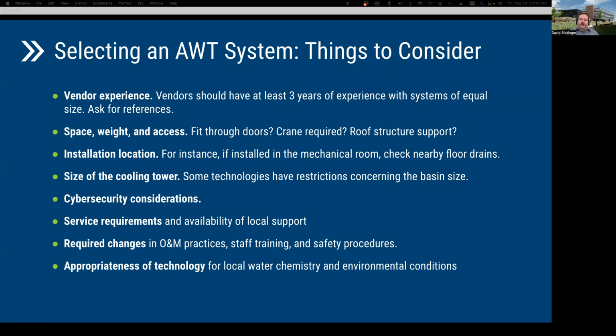One of the projects had to have a custom skid made to fit through a single door to reach the mechanical room. I want to consider if a crane is going to be required, or if you can get by with just installing through freight elevators. And will the floor support the wetted conditions if a reservoir tank is part of that system? If installed inside a mechanical room, it's also a good idea to have a sealed floor with drains.